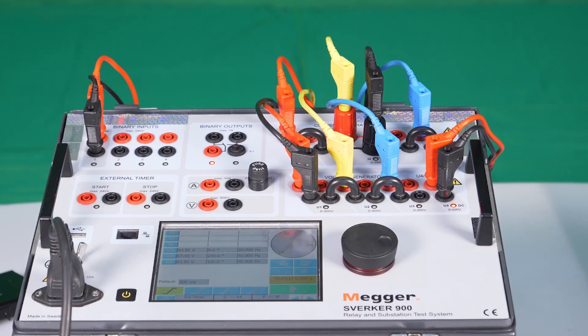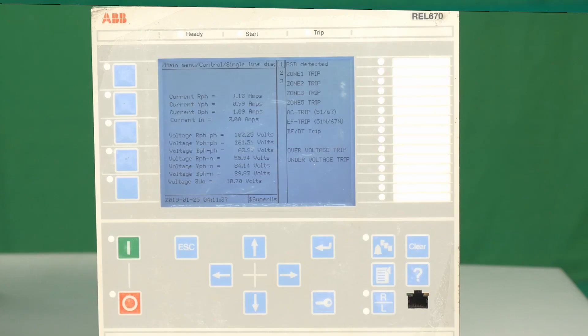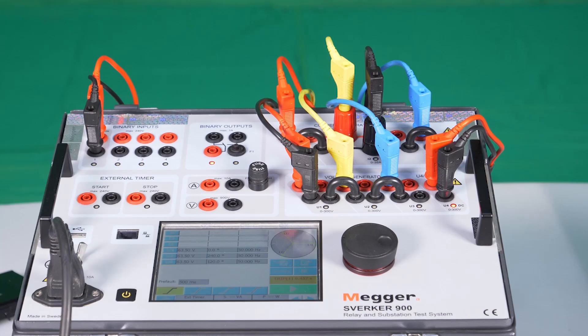ROCOF. Rate of change of frequency application example using ramping. An ABB MAKE REL670 relay is configured for DF per DT with a setting of 0.2 Hz per second.